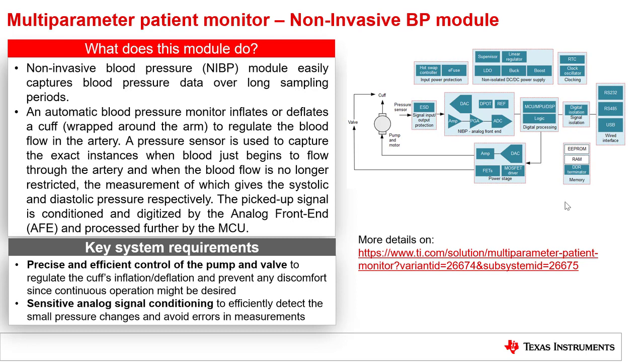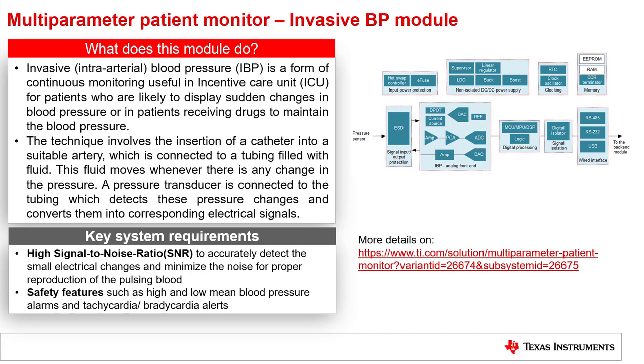The fifth module is an invasive blood pressure, or IBP, module. Invasive or intra-arterial blood pressure is a form of continuous monitoring used in intensive care units, or ICUs, for patients likely to display sudden changes in blood pressure, or for patients receiving drugs to maintain blood pressure. The technique involves inserting a catheter into a suitable artery connected to fluid-filled tubing. A pressure transducer detects pressure changes and converts them into electrical signals. Key requirements include high SNR and safety features such as high and low mean blood pressure alarms and tachycardia or bradycardia alerts.